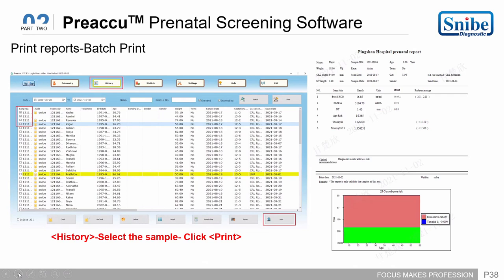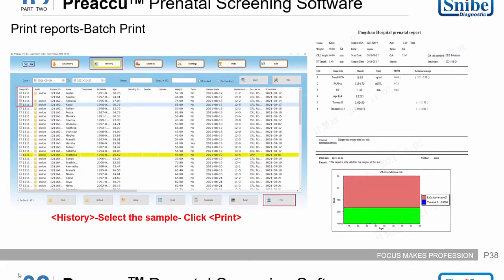If you want to print reports as a batch print, more than one report, you have to go to the history, and then you have to select all reports that you want to print for those samples. Once you have clicked it, this gives you the risk above or cutoff, or your result values along with the trisomy 21 syndrome risks, or trisomy 18 syndrome risk. So this is the process, very easy and user friendly software. You can print either a single report or a batch print.